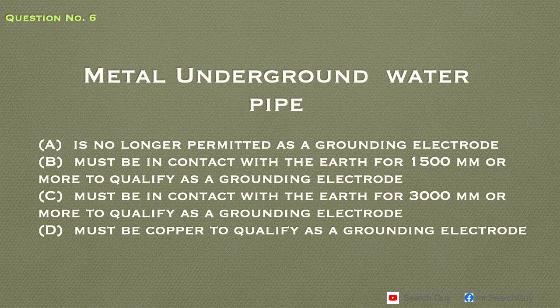Metal underground water pipe. A. Is no longer permitted as a grounding electrode. B. Must be in contact with the earth for 1500 millimeters or more to qualify as a grounding electrode. C. Must be in contact with the earth for 3000 millimeters or more to qualify as a grounding electrode. D. Must be copper to qualify as a grounding electrode. Answer. C. Must be in contact with the earth for 3000 millimeters or more to qualify as a grounding electrode.